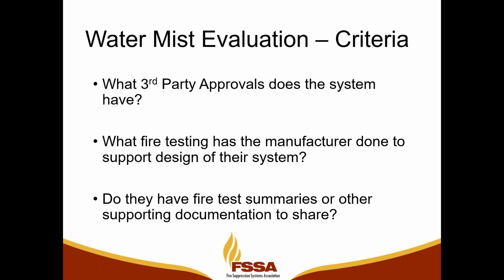There are a number of tests that manufacturers do independently to verify that the system will work and is suitable for that particular type of application. On top of that, once they do the fire test, they will publish fire test summaries or some sort of supporting documentation that they should be able to share with the design engineer, the authority having jurisdiction, the end user, and others, to justify why they are taking this particular design approach for this particular system. Next slide.